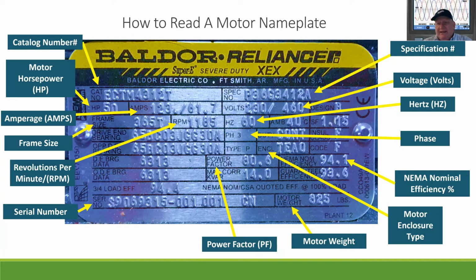The issue is that you can buy motors with various ambient temperature ratings. But a lot of people say, I just want a 50 horsepower motor at 1725 RPM, and they forget about the actual ambient temperature rating of that motor. The other big factor is back to the 1.15 service factor. I want to bring up an issue about VFDs also: when you put them on, because your output waveform is not perfectly sinusoidal, you lose roughly 3 to 5%. So you start running your motor automatically into service factor. Sometimes it's 5 to 10%, depending on the VFD that you're using.